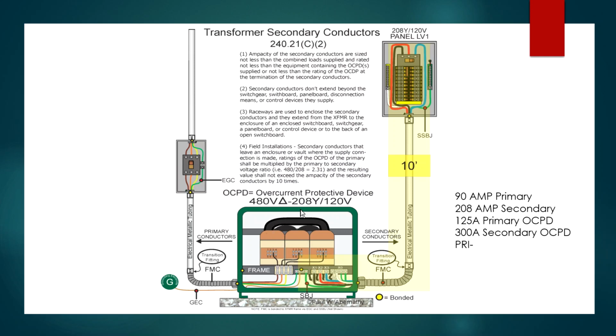Then he selects the type of transformer that needs to be able to handle the loads on hand, based on whatever this device is. So in this case, a 75 kVA transformer, which has a 208 secondary current rating, is perfectly okay here. Could it be larger? Could this have been a 150 kVA transformer, but still only have a 200 amp device here in 3/0 conductors? Absolutely. You don't have to, because I could have had the options to have multiple panels being fed by this transformer. So just keep that in mind. All right, so let's look at what we've got at hand. Now let's assume, forget the 75 kVA at this time. No, let's go on and do the 75. So we're assuming a 75, the engineer designed it, but he said this panel is only going to have a 200 amp device, and this is going to be a 3/0 for argument's sake today. All right, good for 200 amps.